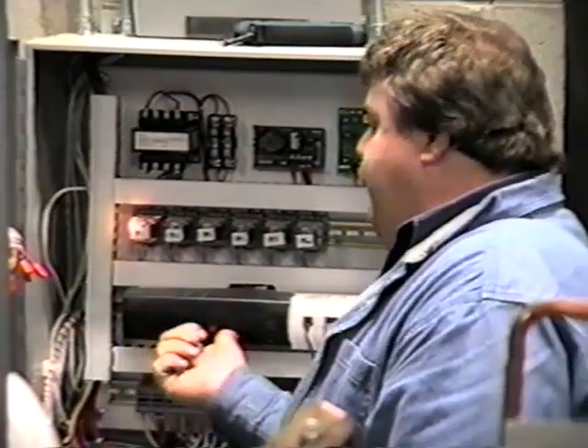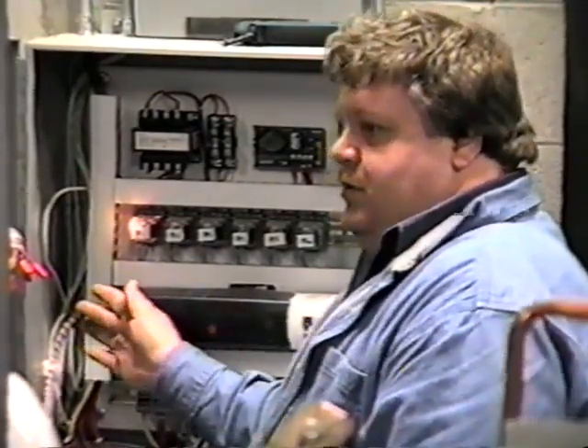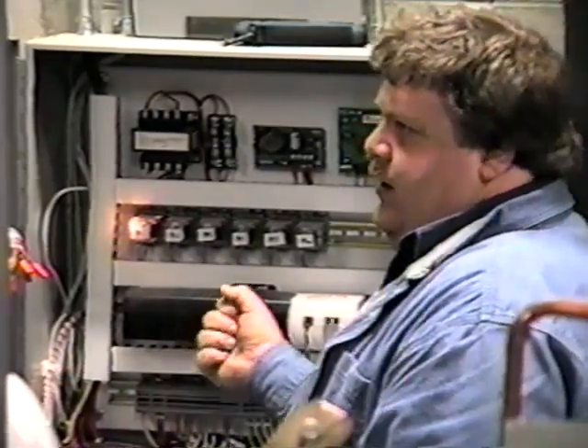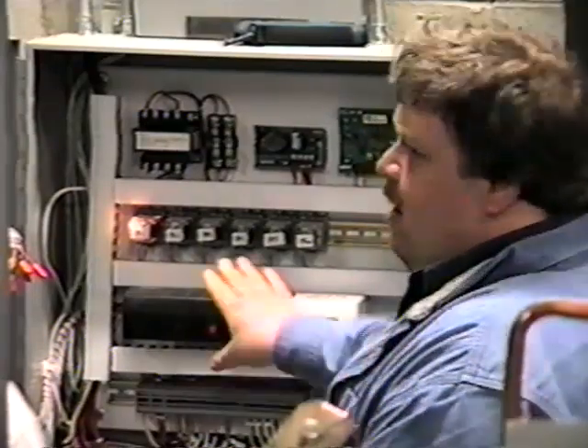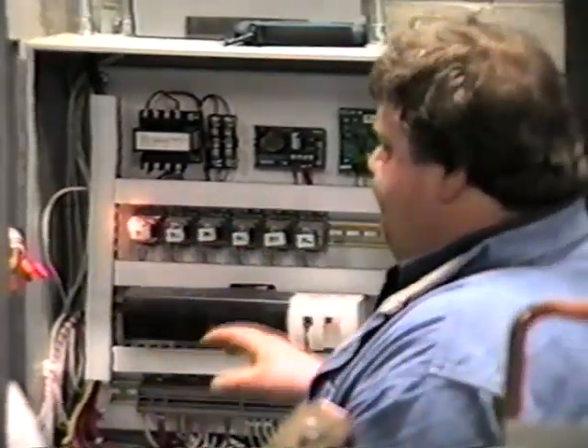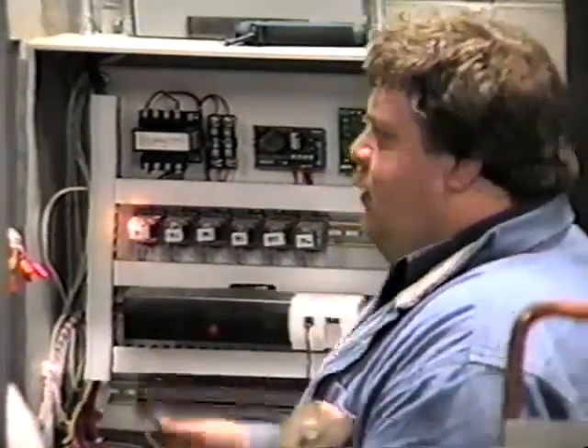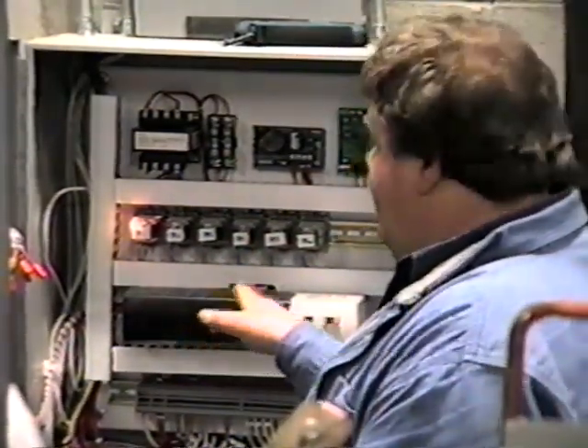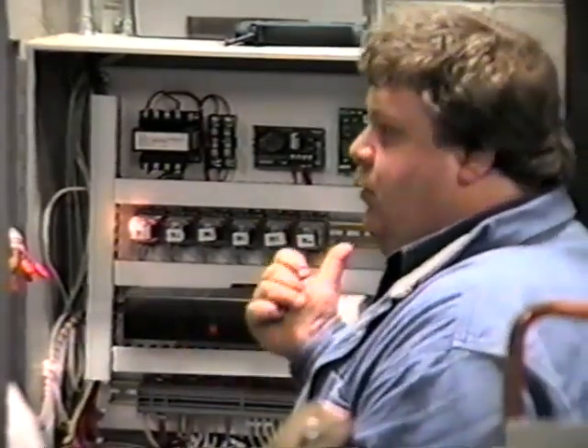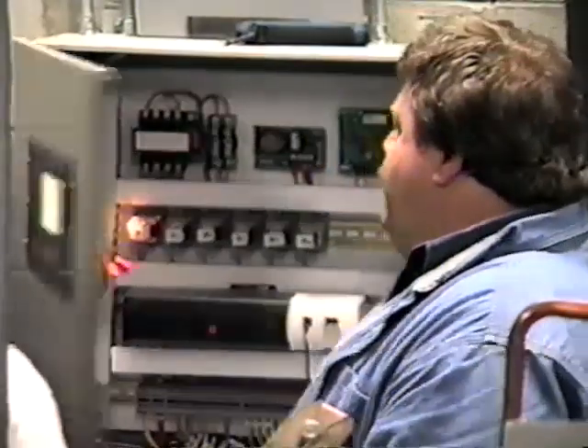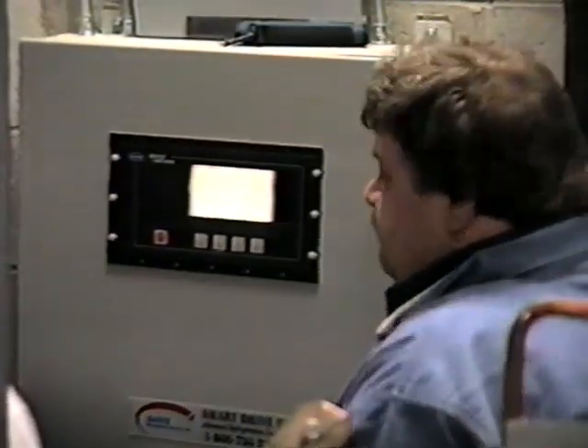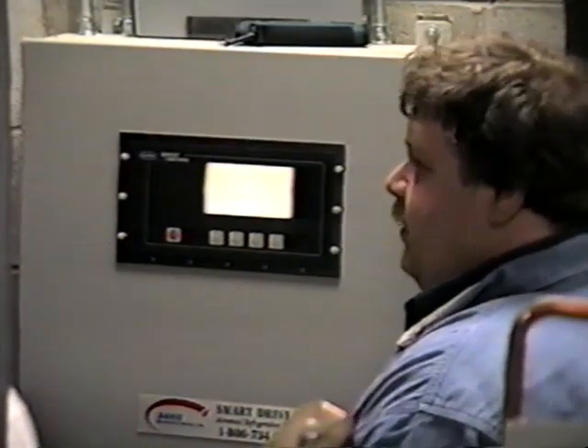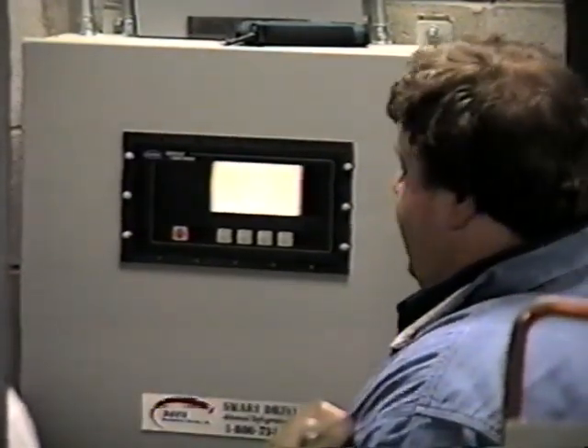So if you want to do other types, if you want to do alarming, all kinds of good stuff. Right now we've got software alarms in this for high ice temperature at 28 degrees, and we've got one other, I can't remember what it is here. I believe it's the low discharge, or low and high condenser water temperature. They're software only, so they're only going to read out here. They're not being physically sent through a contact out. We put that in there so that if they put the bus in here, this will show up as an alarm on their front end package. Right? So down the line, if there's things we want to custom tailor into it, always come back and discuss what you want. It's not an awful lot to modify the program on it.